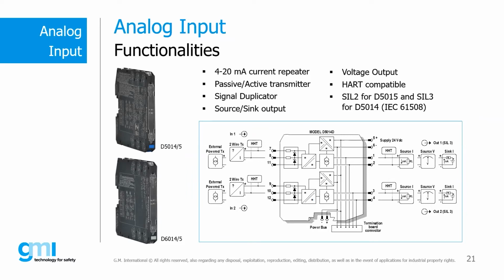So for analog inputs, what can we offer, and what are the main features? We are using isolators that have a 4-20 milliamp current repeater. The input in this case can be active or passive. Some differences you may find with other interlocutors, of course, because active and passive is always a challenging discussion. We say active when the transmitter is 4-wire or 3-wire, so it has a special auxiliary power supply, and the 4-20 loop that goes to our isolator is active. We call it passive when we are talking about a 2-wire 4-20 loop, only 2-wire, so the power supply goes through the 4-20 milliamp loop.